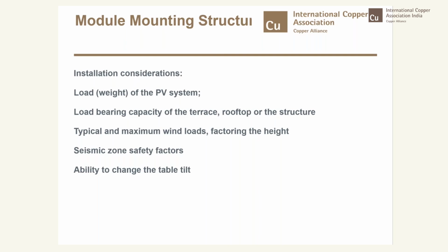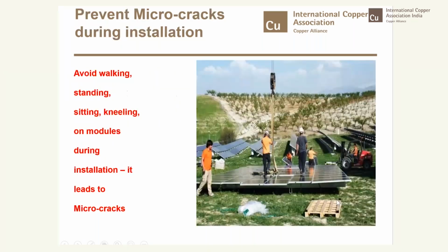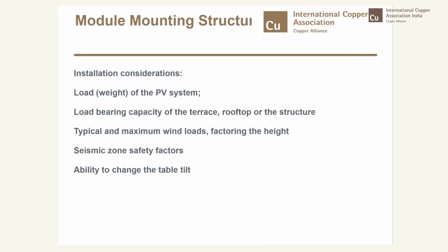When we talk about the mounting structure, we need to consider the load on that PV system. MNRE says that the maximum weight per square meter shall be 60 kilograms. So your design shall be in accordance with that criterion. That is the load bearing capacity of the terrace or rooftop or the structure. And you may have to consider the typical maximum wind load prevailing in that area, including the height, which needs to be factored in.